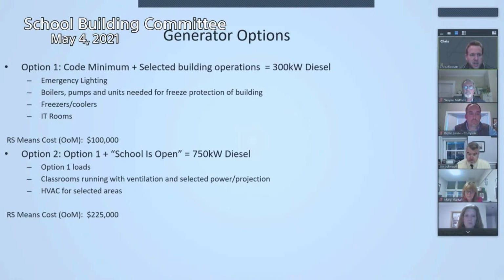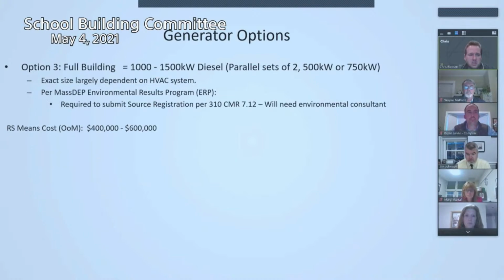The third option is doing a full building generator, that's the 1 to 1.5 megawatt range. There's a lot of variables on it, and one thing we shouldn't lose sight of is that generators of that size may result in some environmental requirements, either reporting or registrations, something you have to talk through.